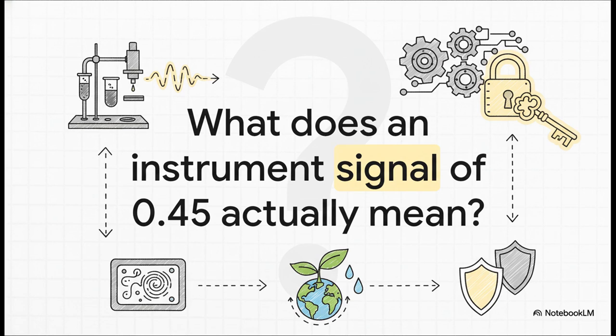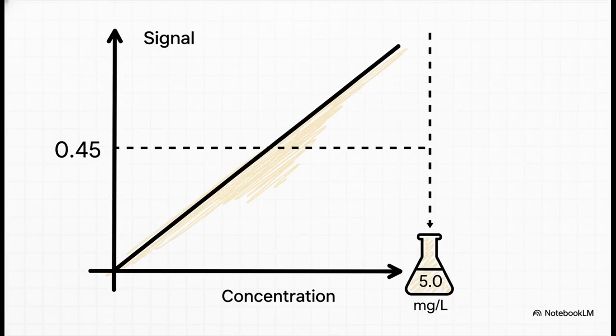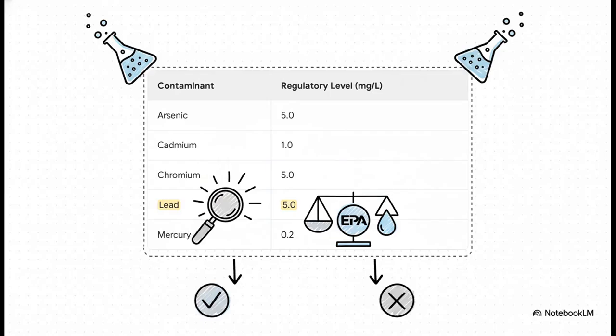It's totally meaningless. But this is where all that prep work we did, this is where it all pays off, because we have the secret code. Remember our calibration curve? We take that signal, 0.45, we plug it right into our equation, and voila, we get our results. A concentration of 5.0 milligrams per liter of lead. We now have our answer. But is that good? Is that bad? What's the verdict? Well, we compare that number against the official regulatory limits set by agencies like the EPA, and you can see here the action level for lead is 5.0 milligrams per liter. Our sample is right at the limit. And just like that, a clear, data-driven decision can be made.